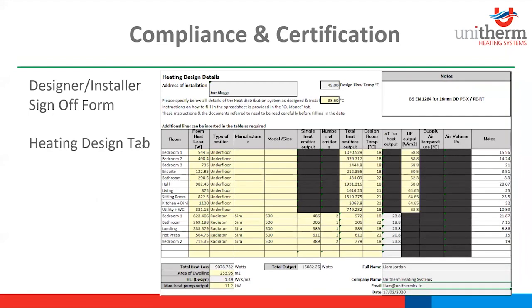Along with the designer installer sign-off, the second part is the heating design tab, completed along with SR50 heat loss calculations. We do this in-house with our system design, done immediately to give correct calculations and outputs for your heating system. This gives total heat loss for the building, total heat output of the emitters installed, and a design heat loss indicator. For example, a total heat loss for this building of 9 kilowatts, total heat output of emitters of 15 kilowatts, with an 11 kilowatt unit running, and a heat loss indicator of 1.49.